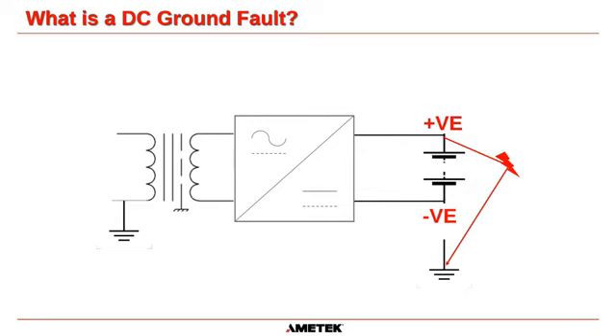Any path to ground whatsoever, if you don't have a transformer, which all houses do not have an isolation transformer, the code says you have to have neutral connected to ground to give a return path to clear any breakers and prevent people from getting electrocuted. So it's got nothing to do with DC ground faults. It's more about personal and fire safety for why we do grounding in buildings. Hopefully that explains what you're asking.